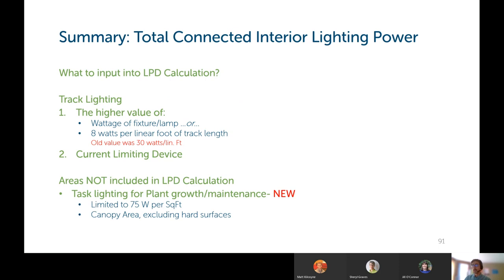Other areas not included in the lighting power density calculation are task lighting for plant growth and maintenance. This is new. There's a limit to how much you can install there. It's 75 watts per square foot of plant growth and maintenance area, including canopy area, but not hard surfaces that you would be doing work on. And there may be some more clarification on that in the final language of the code that I will be checking on.